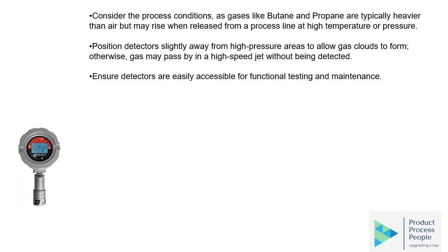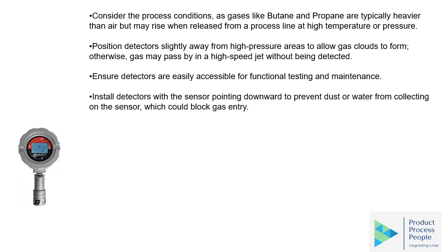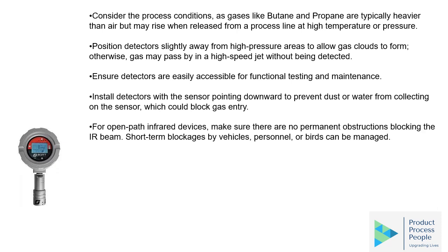Ensure detectors are easily accessible for functional testing and maintenance. Install detectors with the sensor pointing downwards to prevent dust or water from collecting on the sensor, which could block the gas entry.